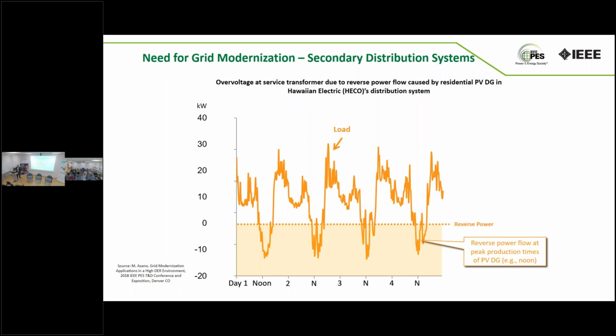So what they have in that neighborhood is PV, photovoltaic distributed resources behind the meter being served by that transformer. Around noon every day, the amount of PV output in that neighborhood exceeds the local load, and the transformer starts exporting or injecting power to the grid. It happens every day. Some days are cloudy, some are very sunny, and the rest is basically typical. There's a peak in the evening, etc.